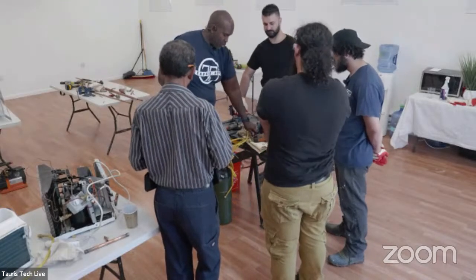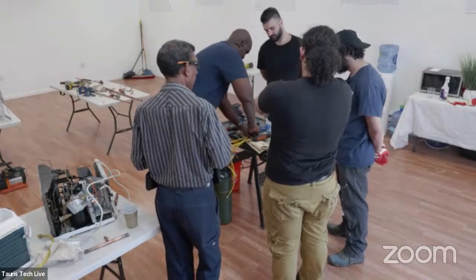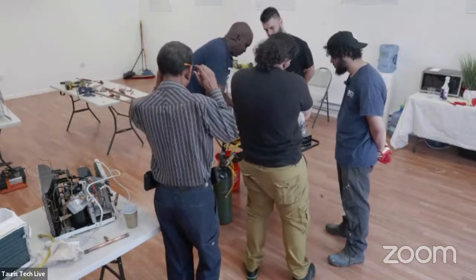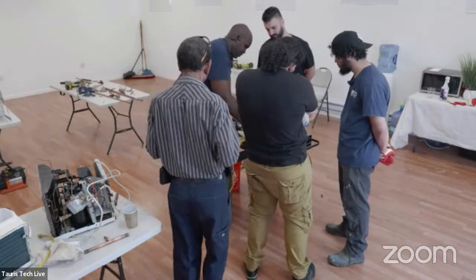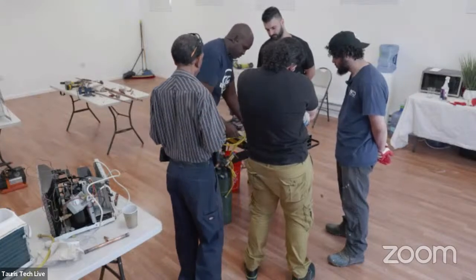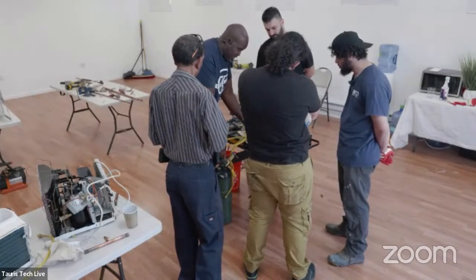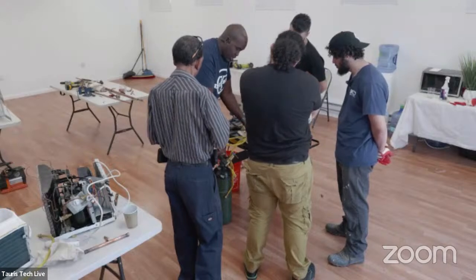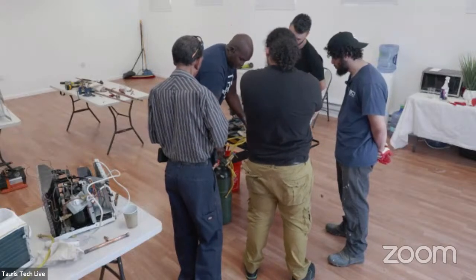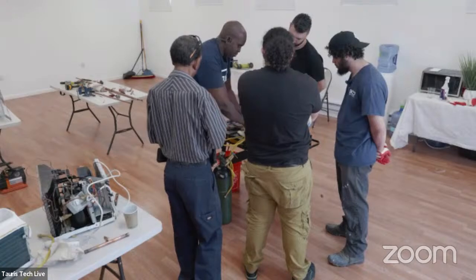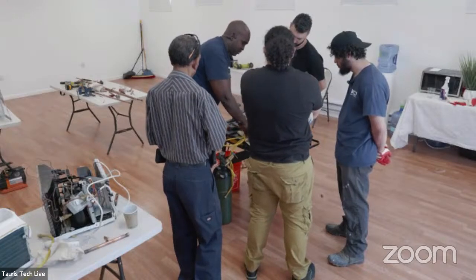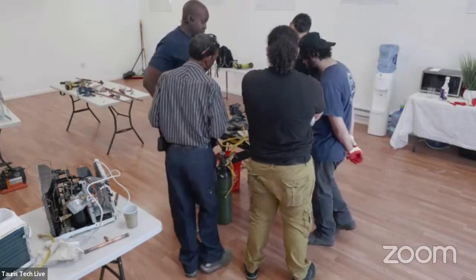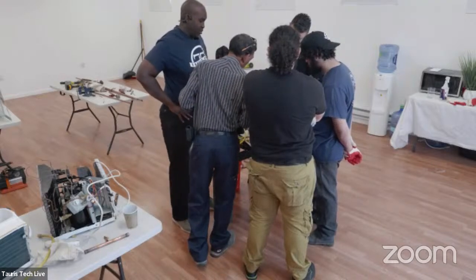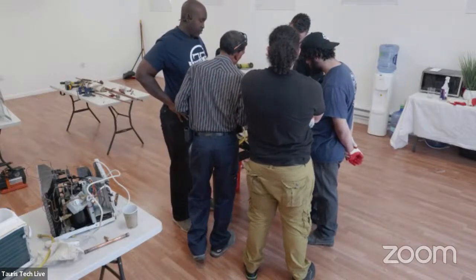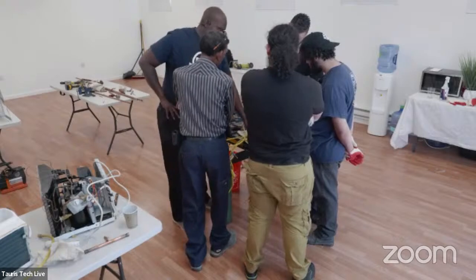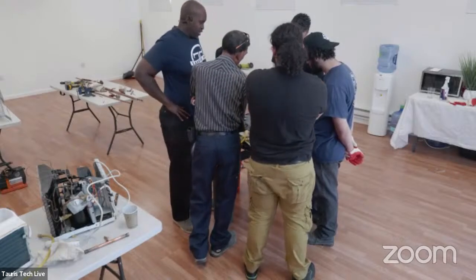So we open, the regulator is still open, so I just pushed in what was in the regulator, and then I need to close this back. I see it's still going up, so it looks like it's holding, because the pressure has to settle. So it's just a question of how long it takes to settle.